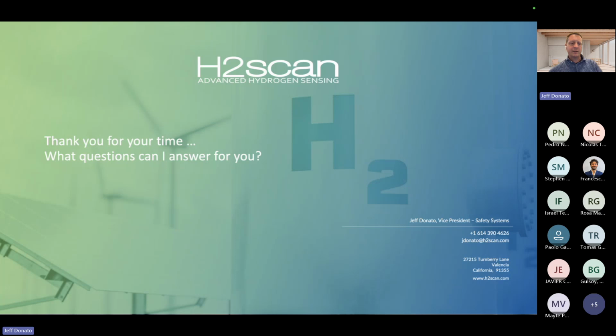A lot of the solid state sensors, like one of our sensor technologies, for example, are hydrogen specific, and there is a physical barrier that no other molecules can get through. Since hydrogen is so small, helium might be able to get through because it's small as well, but everything else is blocked because it can't enter the substrate. Other systems do it algorithmically with firmware and conditioning to make it hydrogen specific. But yes, we do recommend that it's not just a general sensor, it's definitely a hydrogen specific sensor.